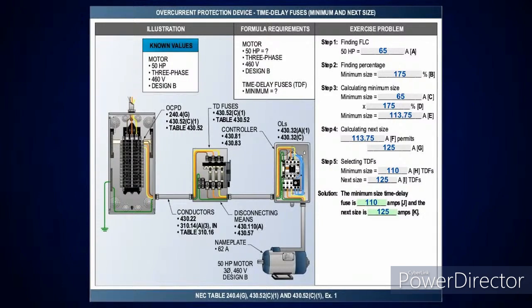We're using the same motor. The only difference here is I'm doing a time delay fuse. Okay. And if you go look at the table and you pick up your time delay fuse squirrel cage, it's going to tell you take it at 175%. So you just take 65 amps at 175%. That gives you 113.75. The next size below that is 110. I'm automatically permitted to go up to the next size if I want to. So I could have 110 as a starting point, or I could go up to the next size due to inrush current because the 110 amp didn't hold it, and go to a 125 amp.